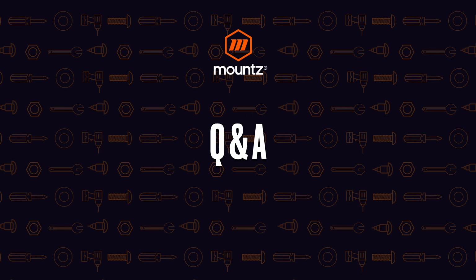All right, Dave, thanks. Another question we had was, before the calibration process starts, is there like a warm-up you have to do with the torque tester or some type of process? So typically, you're going to want to exercise, again, the sensor for at least a minute or so at 100% of the rated value for that tool. And then you can also have that within the lab for 1 to 2 days before to make sure that there aren't any changes to any of the other componentry and that there is a complete equilibrium with all of the components.